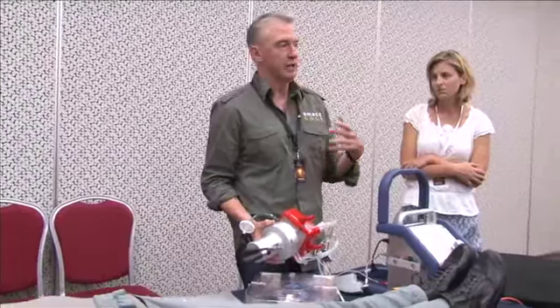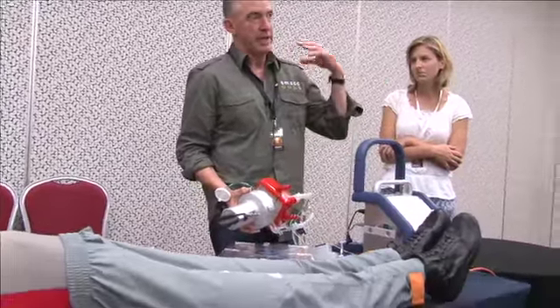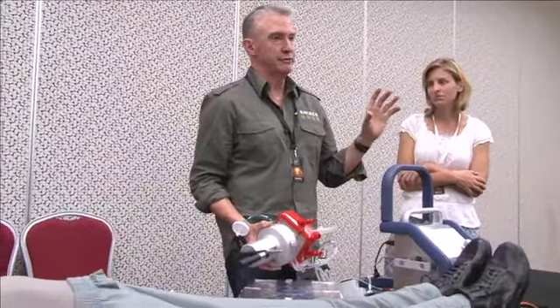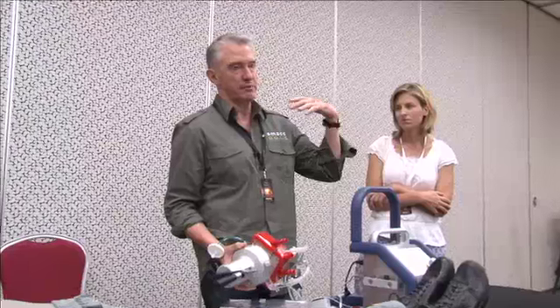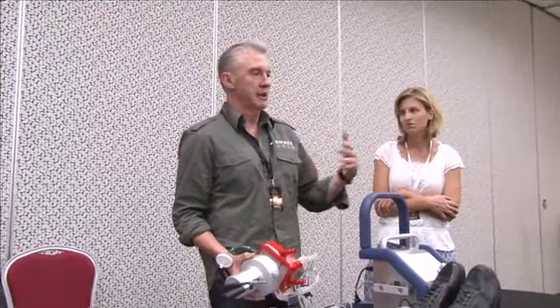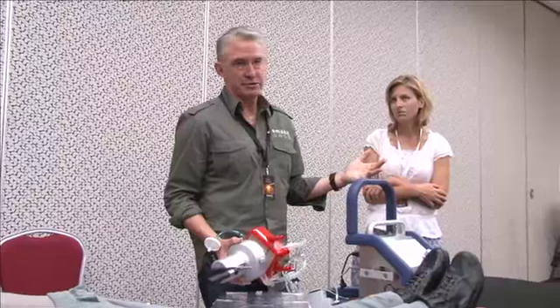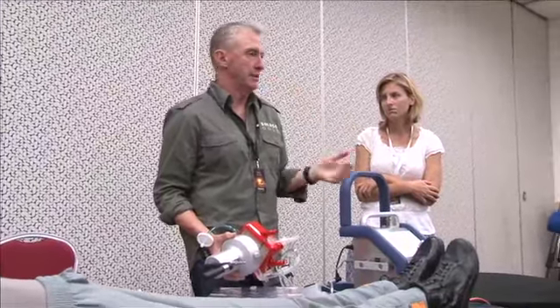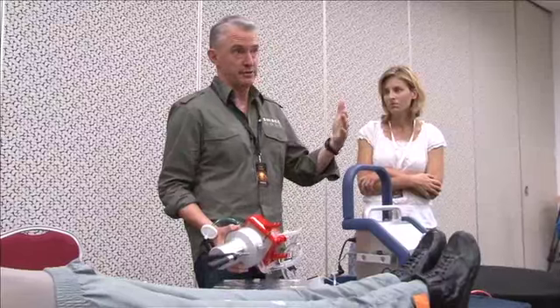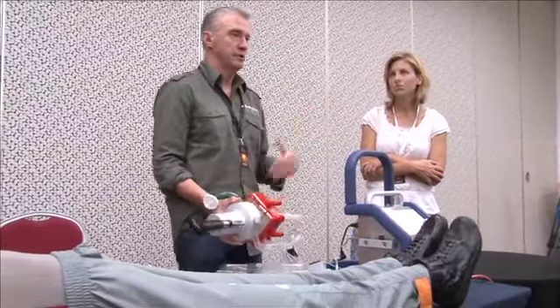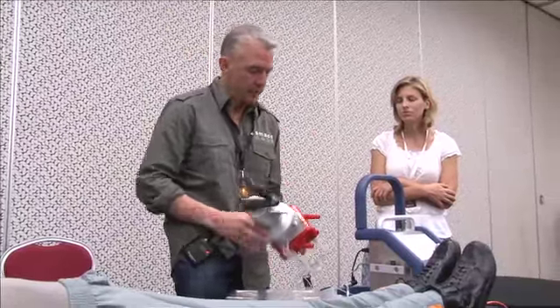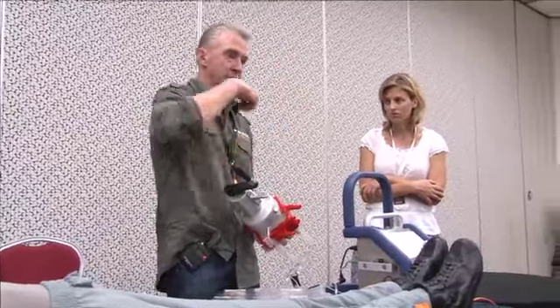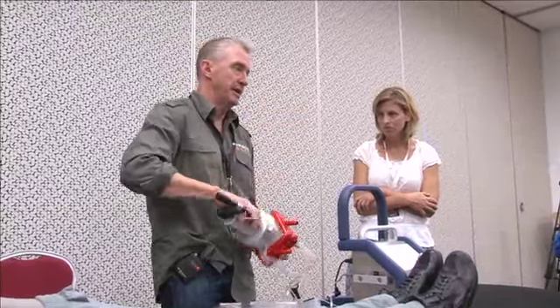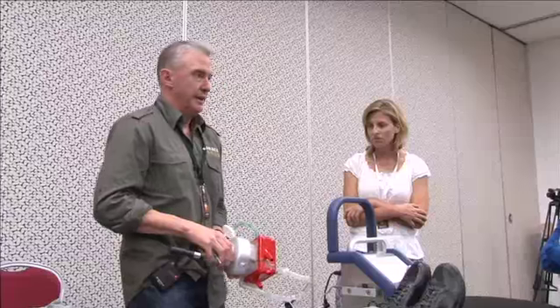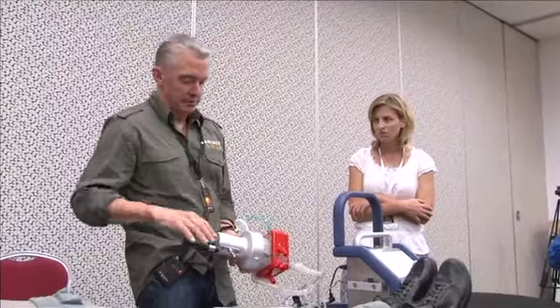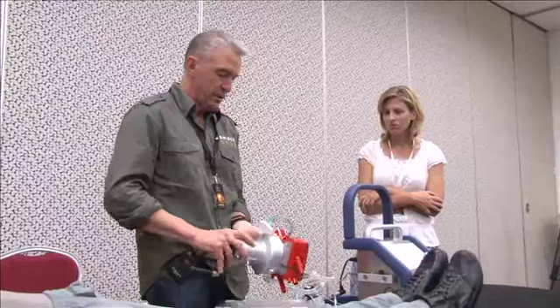It also means that you've got to have a certain RPM rate to even have zero flow. So because the pump is working against an afterload, depending on what the patient's pressure is, you may have an RPM rate of maybe 1800 RPM just to have zero flow. So before you go onto ECMO, you've got to have the pump lines clamped, turn the RPM rate up, and then open the clamps. So turning this is actually fairly easy.